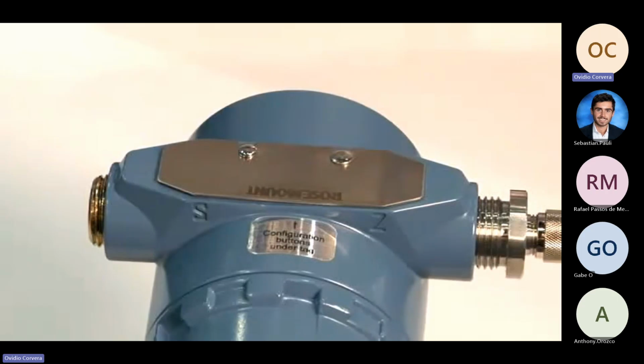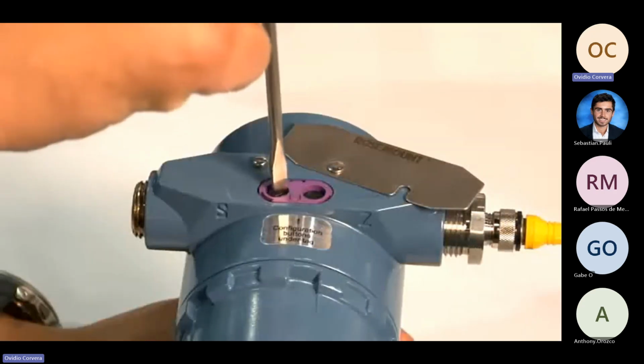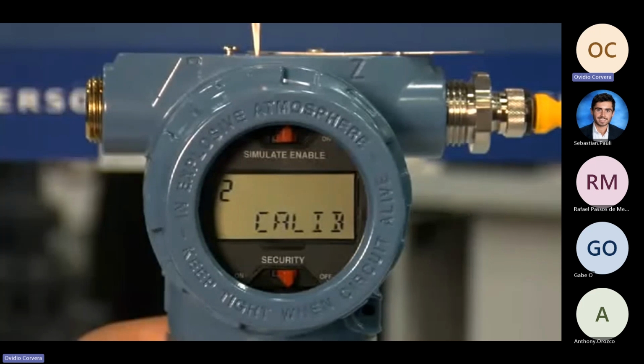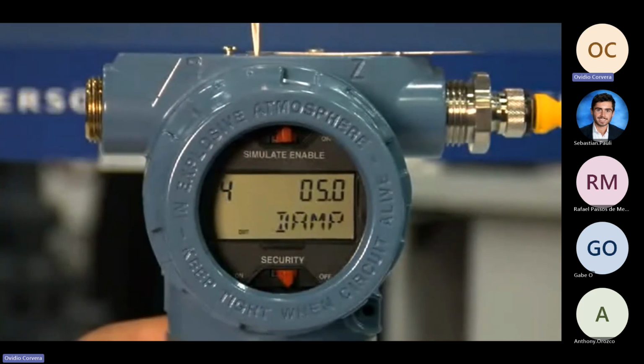First, you can see that the buttons are easily accessible and clearly labeled external to the transmitter housing. This is a must for configuration or maintenance in a hazardous area because you don't have to remove the electronics cover. To activate the LOI, you can push either button on top of the transmitter. And this shows us a simple and responsive menu that allows for fast and efficient commissioning. This menu design was created using Emerson's new human-centered design processes, which ensures the menu is as intuitive to use as possible. So now that we've done an overview of the LOI, let's commission a device.